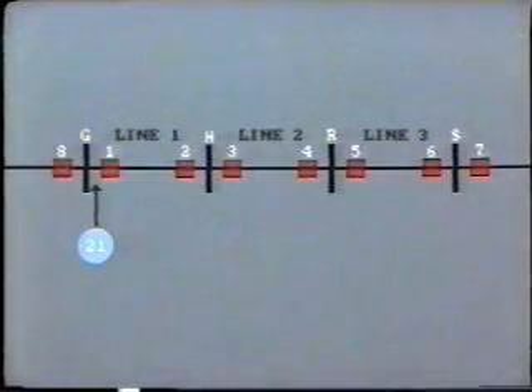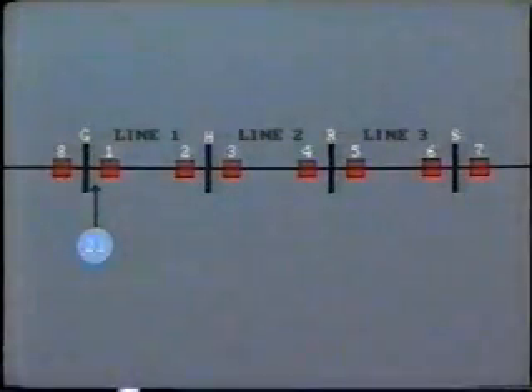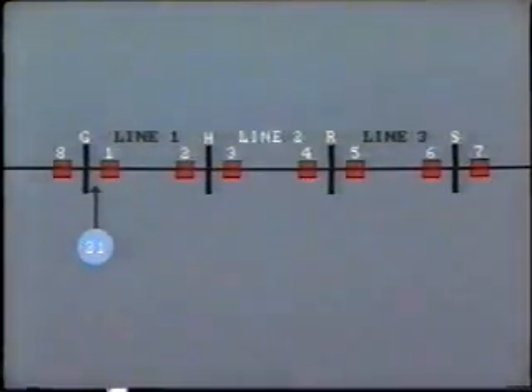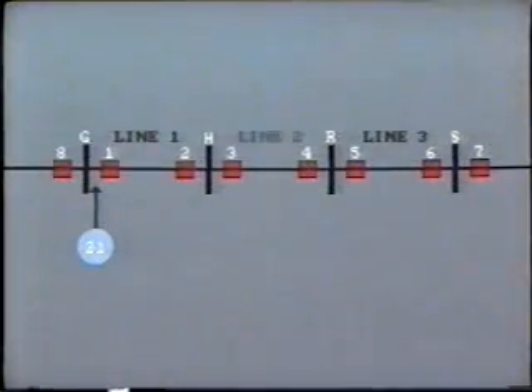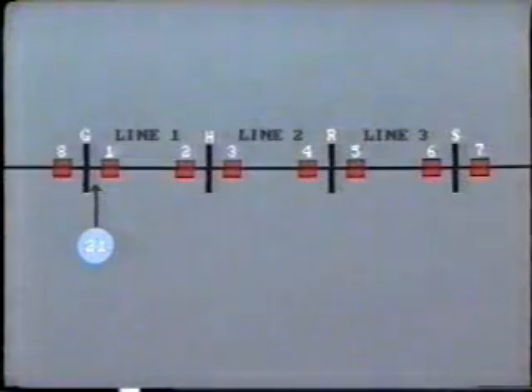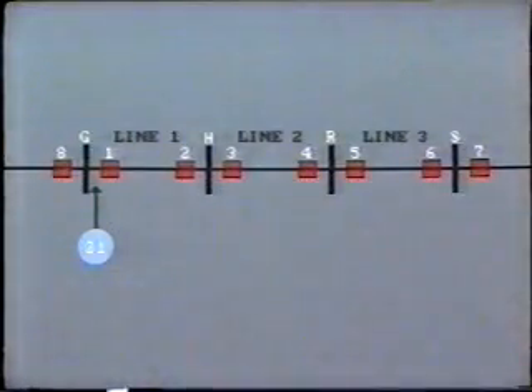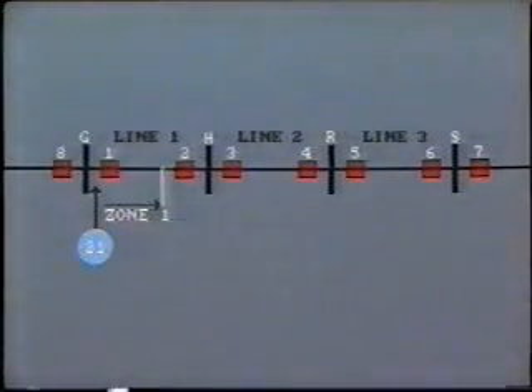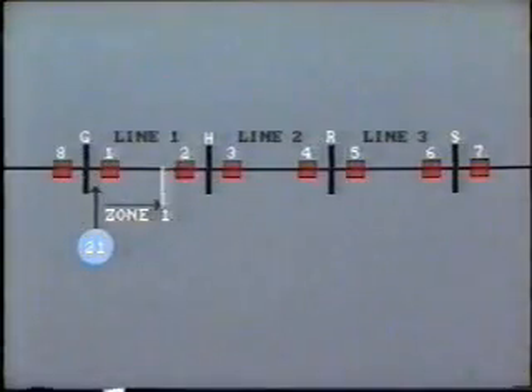Why is this? Well, the main point is we do not want this relay on bus G to trip for faults on transmission line 2, that is, between buses H and R. Therefore, in order to allow for any impreciseness in actual operation of the relay or the power system, Zone 1 is set to operate up to about 80% of the line.